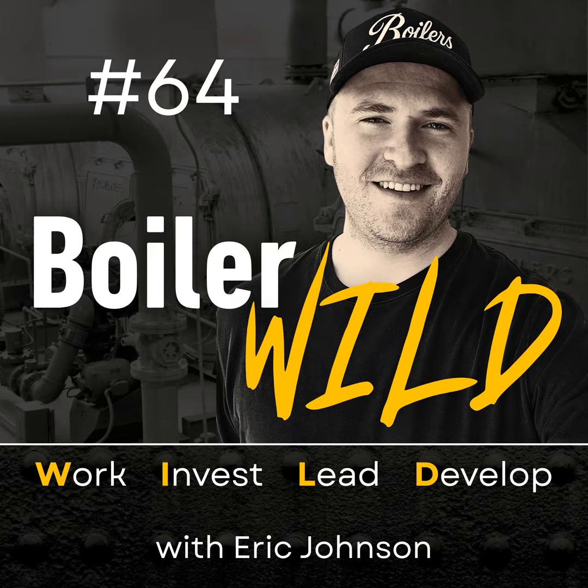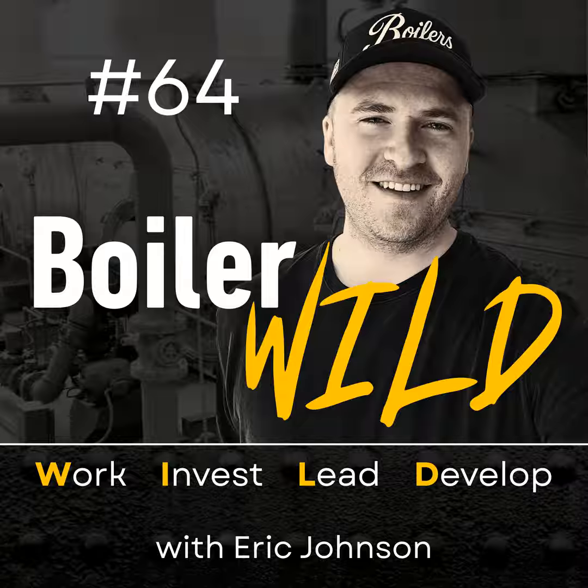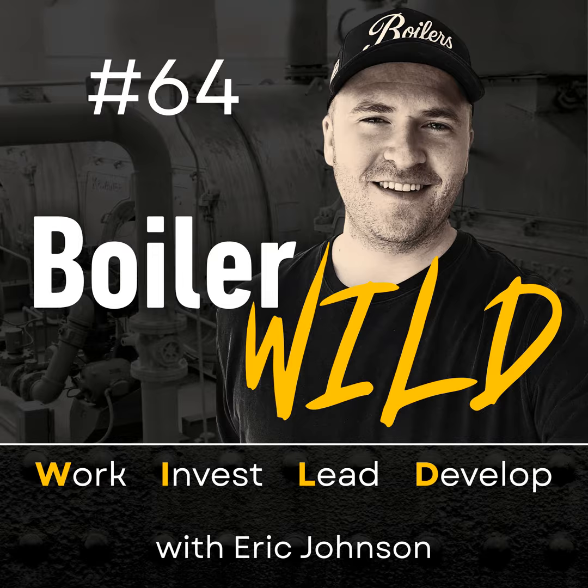So you reach out, you push the little button on the front, the little red button, typically on a Honeywell pressuretrol for a manual reset. You push the little red button, you hear a little click, and then you hear the blower motor start, and everything is good to go, and you ride off into the weekend like a happy sailor. So that is a common situation when the boiler is hydroed.